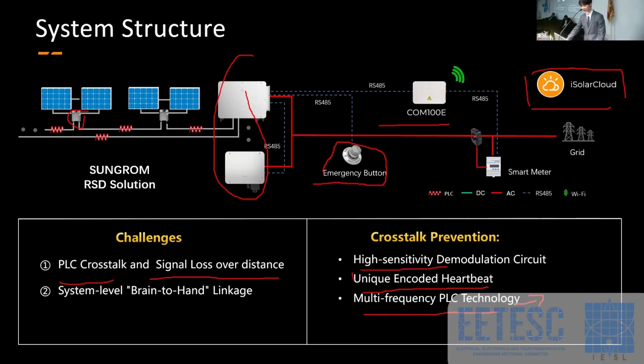And for this one, I would like to give you an example, the unique encoded heartbeat. When you do the installation, you put a lot of the DC cables into a tray. So inevitably, string A's heartbeat signals will be influenced by string B. So we programmed the string heartbeat signals with a unique ID, string A with its ID and string B with its ID. So string A cannot understand string B. Even if there is PLC crosstalk, they cannot understand each other. I would like to give you a metaphor: if soldiers cannot tell you the correct secret code, then he is a spy. It's similar to this crosstalk.